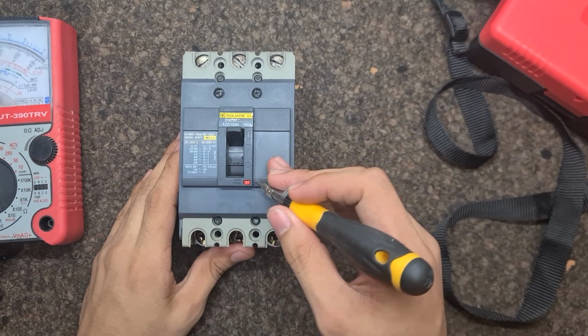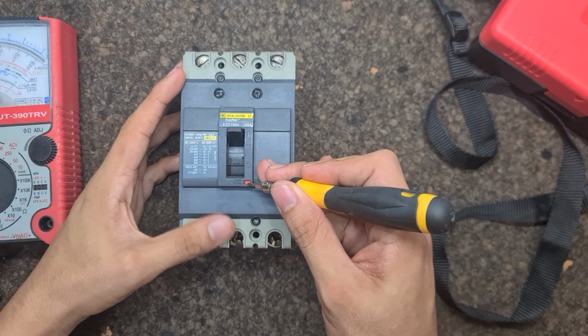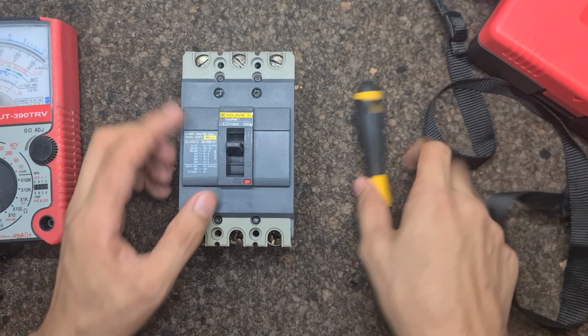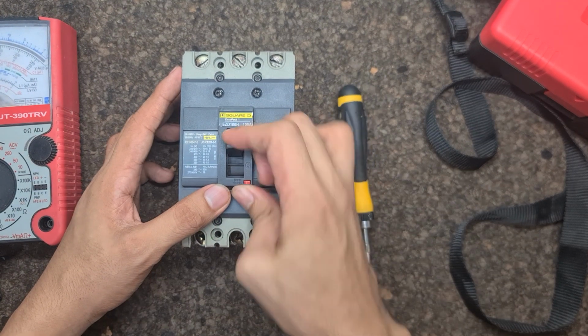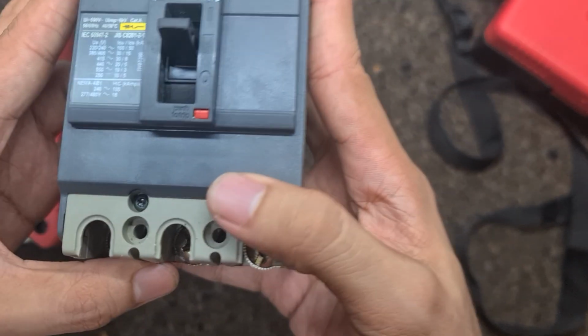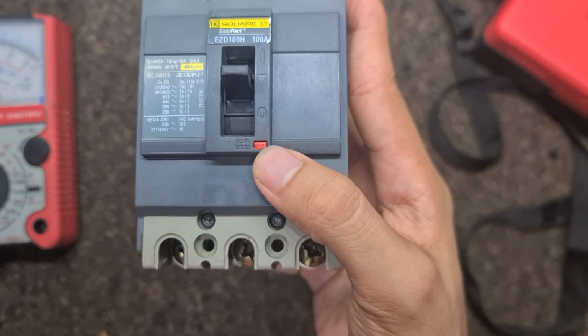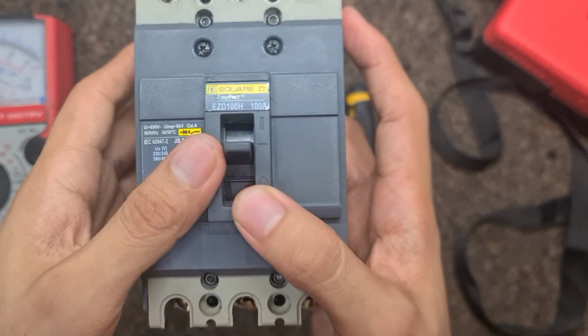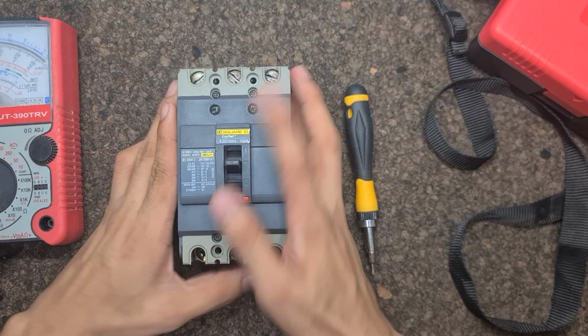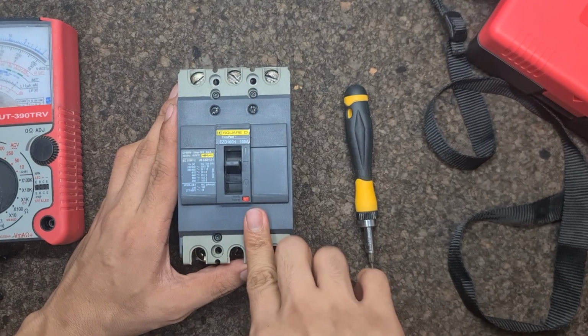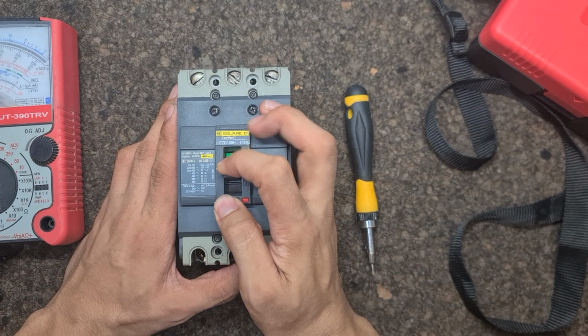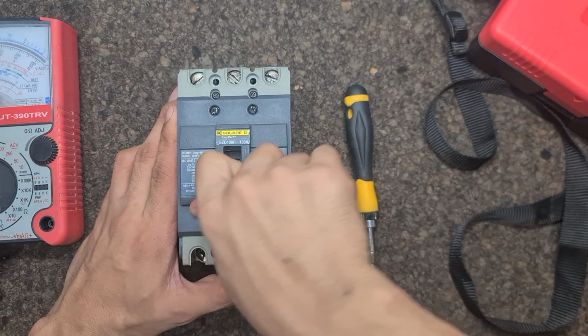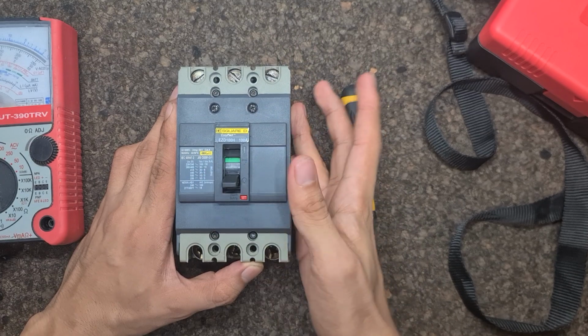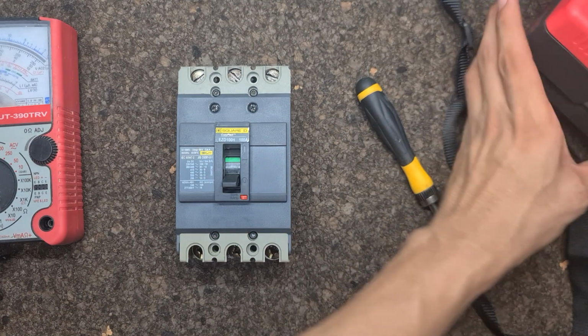Also, most electricians do a push to trip test just to check if the breaker is still okay and functioning. But this test only checks if the protective mechanism of a breaker is still intact and functioning. The trip position is another indicator or sign that a breaker encountered a fault or overloading without doing the push to trip test. Once normally operating, it cuts off the electrical supply.